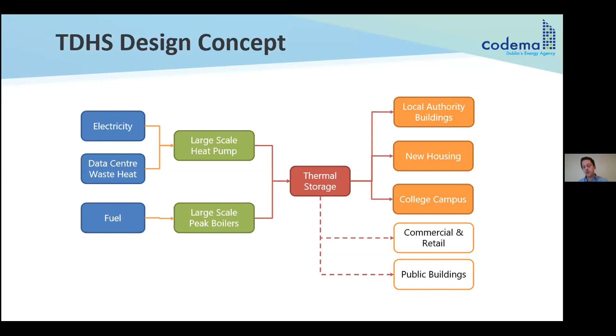A bit more detail on the heat pumps: they're 2-stage heat pumps, essentially 2 compression cycles, so it's kind of 2 heat pumps bolted together, which allows us to maintain really high efficiency but also deliver high temperatures. That's important when you've got older buildings connecting to the network that don't have fabric upgrades, so we can still supply at the temperatures you'd expect from a boiler without needing to retrofit those buildings.